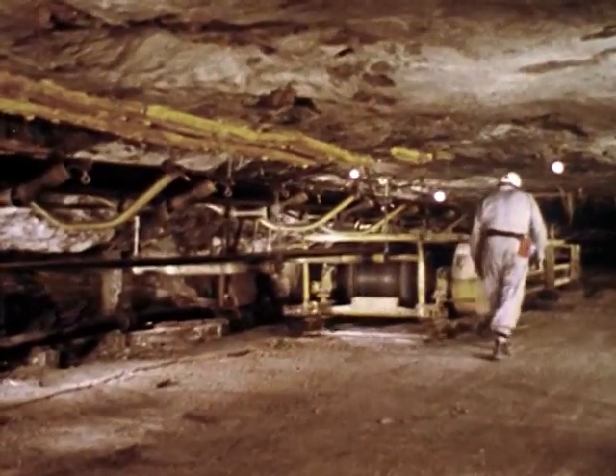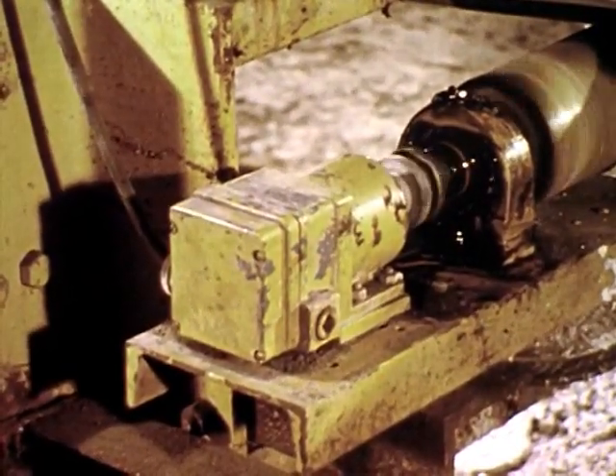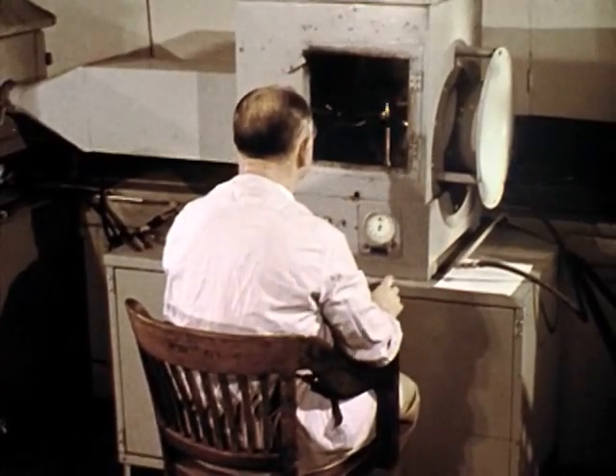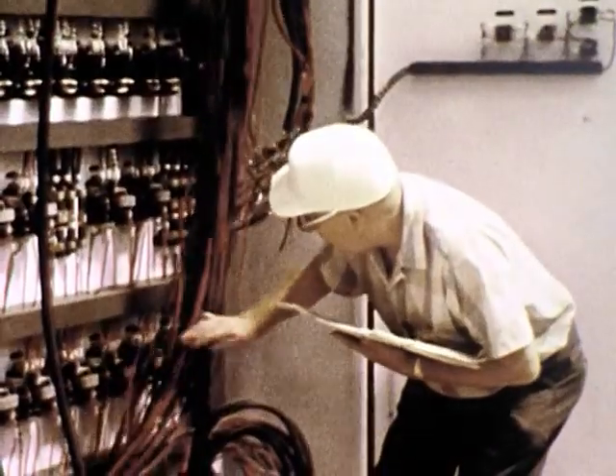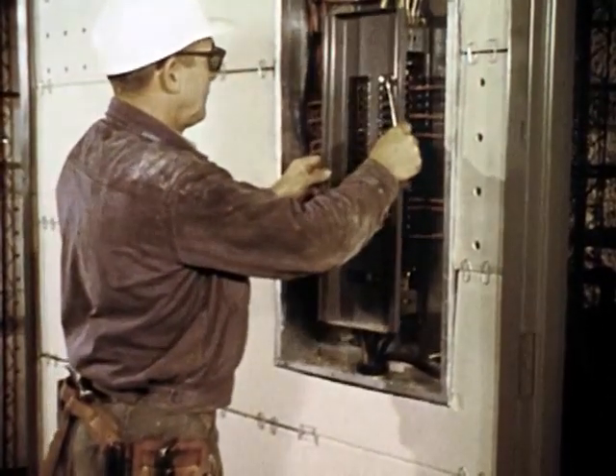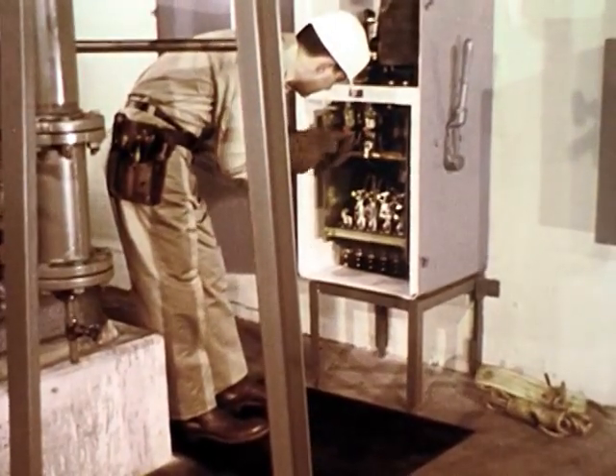Frictional heat may develop at any place along a moving belt where it rubs against a stalled part or obstruction. This can be overcome by having control switches in the driving motor installation that will automatically stop the motor when the belt slows down, slips, or stops. To prevent belt fires, all belts should be fire resistant and the entire belt system carefully aligned. To prevent electrical breakdowns and overheating, the importance of first-class electrical installation, including properly rated switches, circuit breakers, resistors, and conductors, cannot be emphasized too strongly.